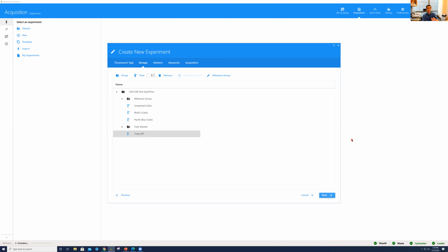The issue now is with a technology like this, where you look at the full spectrum. This is the brilliance of this technology: you can really distinguish between two very similar fluorochromes. But on the other hand, if you don't apply best practices, you're going to run into problems. If you use a slightly different fluorochrome, this technology can distinguish between that control and the sample as being two different fluorochromes.